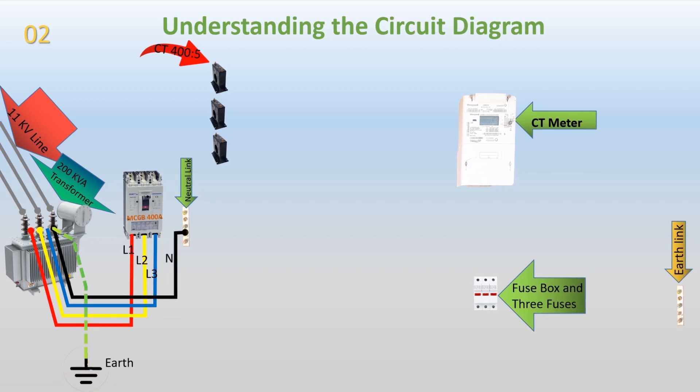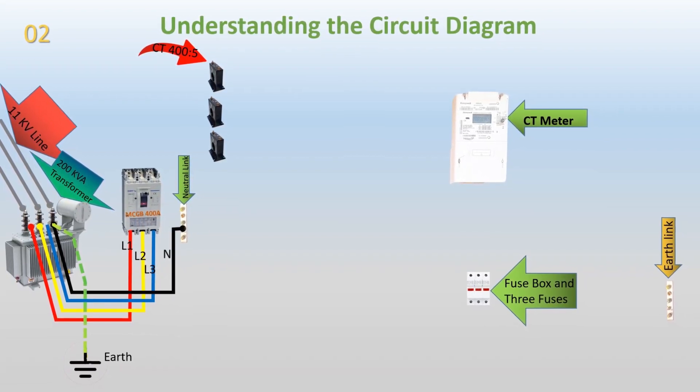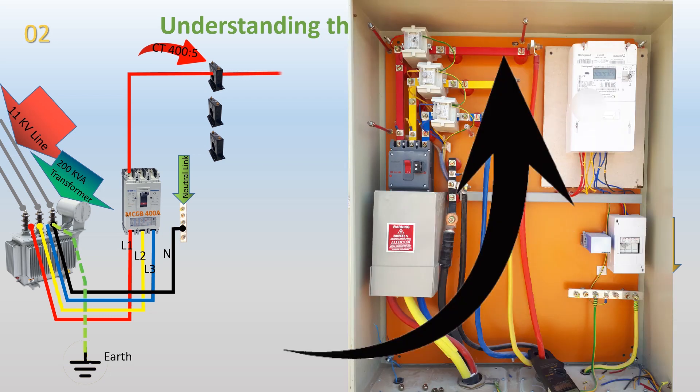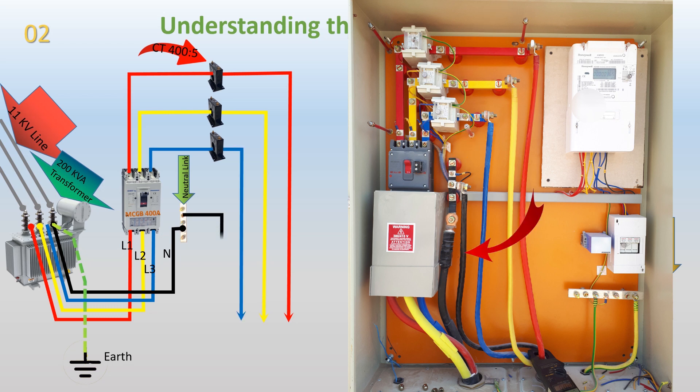Power circuit completion. The L1 phase from the output of the 400A MCCB passes through the first CT, CT1, and then proceeds to the distribution board or load. Similarly, the yellow, Y, and blue, B, phases pass through the second and third CTs respectively before reaching the distribution board or load. A neutral wire from the neutral link connects to the load, ensuring a complete power circuit.